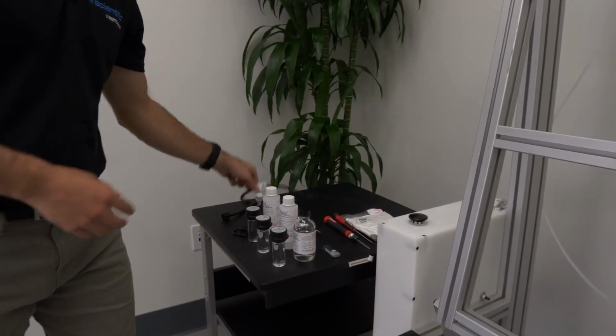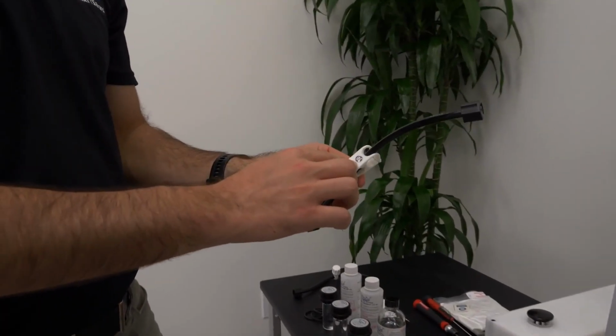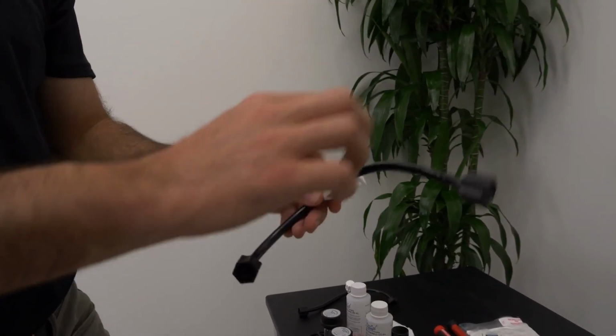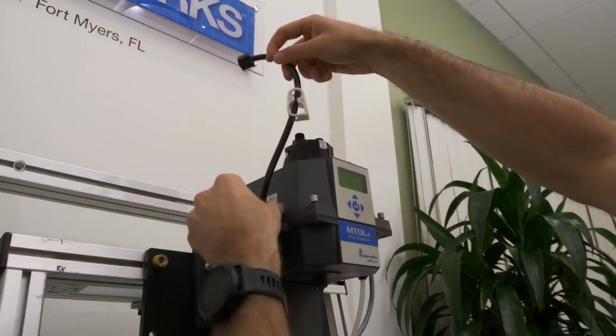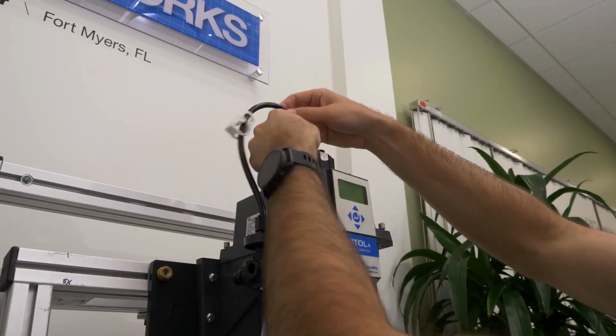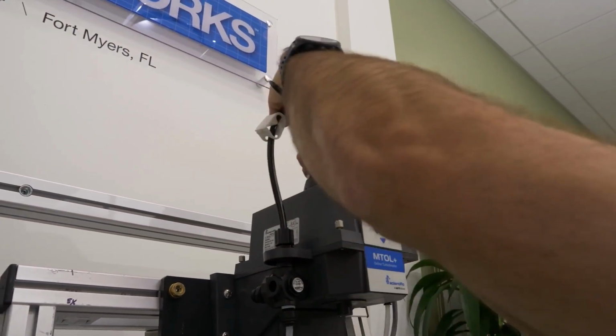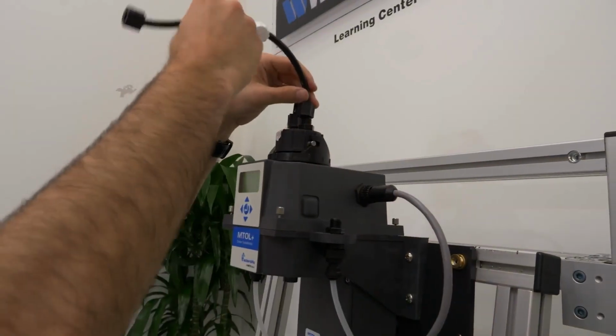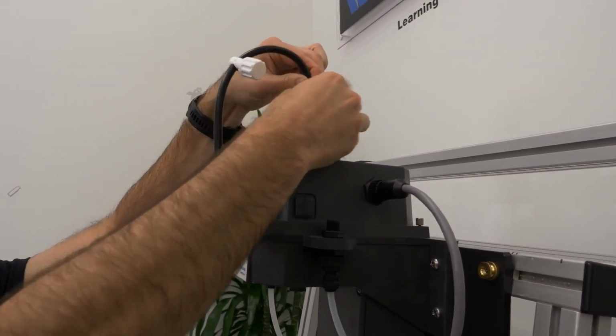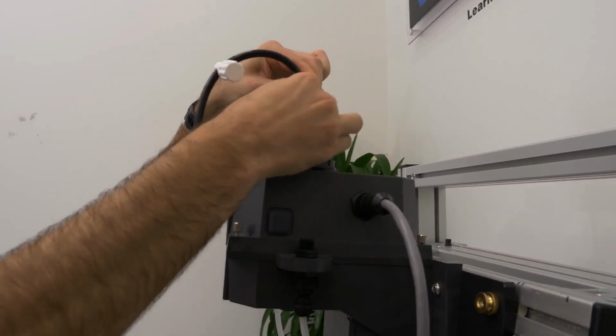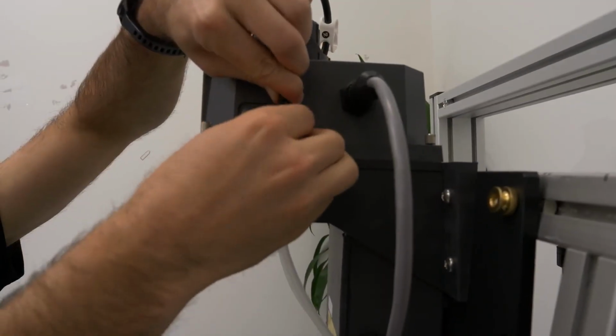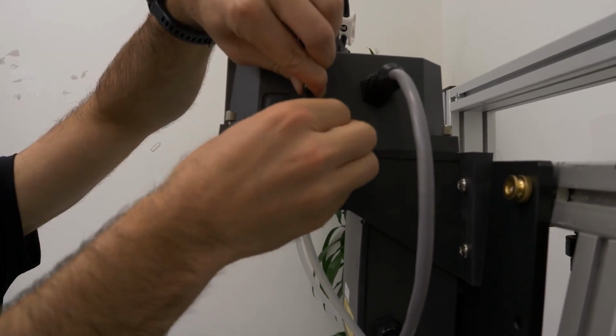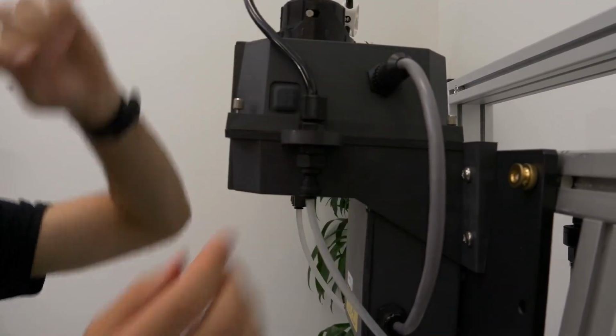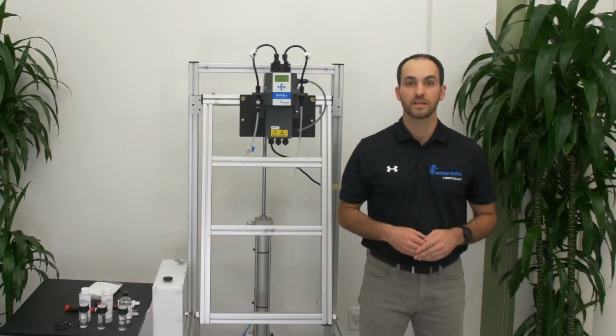Open the tubing kit provided with the analyzer. On the inlet side, the side with the regulator, connect the tube with the shutoff valve using the threaded fitting and then to the inlet port on the top of the flow head. On the outlet side, connect the tube with the back pressure valve to the outlet of the flow head and the top of the quick connect fitting for the drain. Both the inlet and the outlet have 1/4 inch quick connects to make the plumbing very easy.